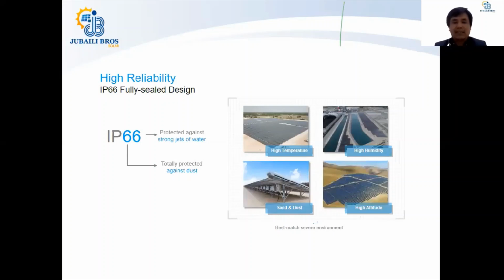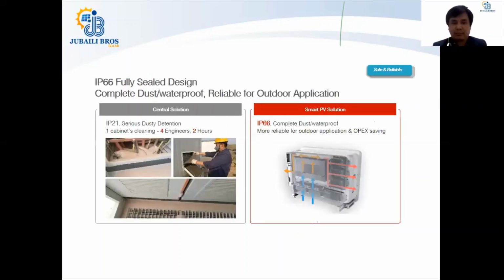Again, talking of reliability, the IP rating has been increased to IP66, which now makes it resistant against strong jets of water, and it is totally protected against dust, which makes it okay to be used in PV plants on lakes as well, for floating PV systems. We have all our electronics compartment fully sealed. With the new range of Huawei 100 KTL, Huawei has used fans as well, which are placed at the bottom backside of the inverter, which take air from the bottom end of the inverter to the backside of the inverter, and the airflow goes out from both sides of the inverter.